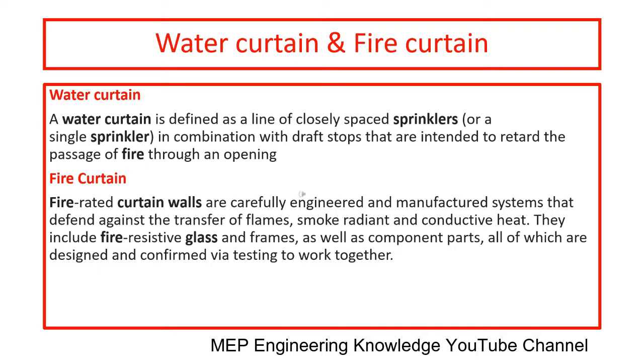In the sprinkler system, there are two more classifications, that is water curtain and fire curtain. The water curtain is defined as a line of closely spaced sprinklers or a single sprinkler in combination with draft stops that are intended to retard the passage of fire through an opening. Fire curtain: fire-rated curtain walls are carefully engineered and manufactured systems that defend against the transfer of flames, smoke, radiant and conductive heat. They include fire-resistive glass and frames, as well as component parts, all of which are designed and confirmed via testing to work together.